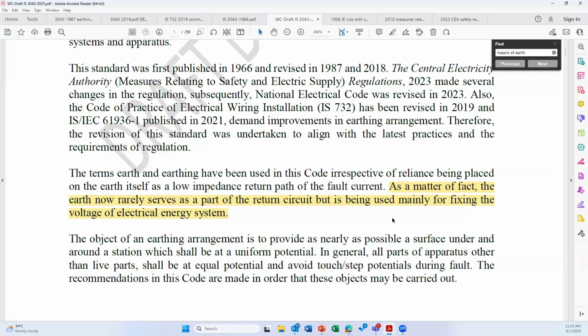Normally, we think that the whole fault current goes through the earth electrode to the general mass of earth, then flows through the general mass of earth to the source, which is absolutely not correct. The amount of fault current that flows through the earth electrode is negligible. It will be very, very low in comparison. For example, sometimes there is an Excel calculation which is widely used in our country. Earth electrodes are designed for fault current dissipation of 50 kiloampere, I'm saying for 230 volt application, 400 volt application, 50 kiloampere fault current, 25 kiloampere fault current, 30 kiloampere fault current.